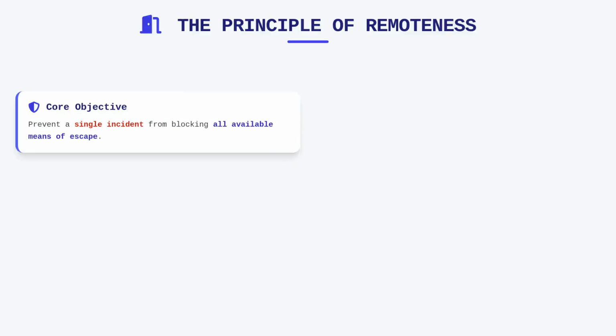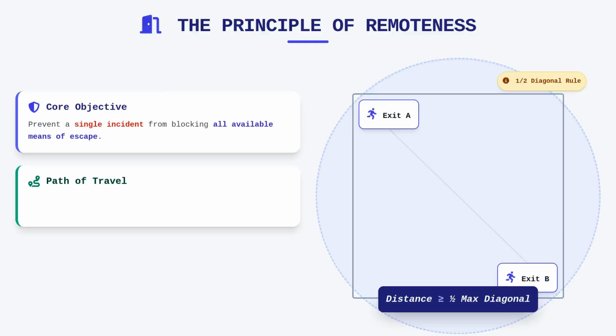Geometric arrangements within the floor plan are governed by the principle of remoteness, which prevents a single incident from blocking all available means of escape. The standard rule of thumb for many occupancies is the 1/2 diagonal rule, which mandates that the distance between two exits must be no less than half the length of the maximum overall diagonal dimension of the building or area served. If a floor plan is complex or irregular, this measurement is taken along the natural path of travel, not just in a straight line through walls.